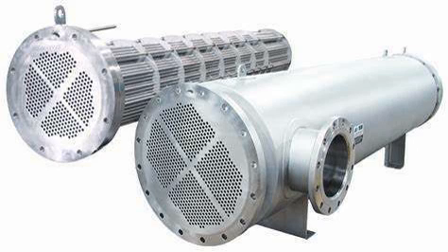longitudinally finned, etc. Shell and tube heat exchangers are typically used for high-pressure applications, with pressures greater than 30 bar and temperatures greater than 280 degrees Celsius. This is because the shell and tube heat exchangers are robust due to their shape. Several thermal design features must be considered when designing the tubes in the shell and tube heat exchangers.